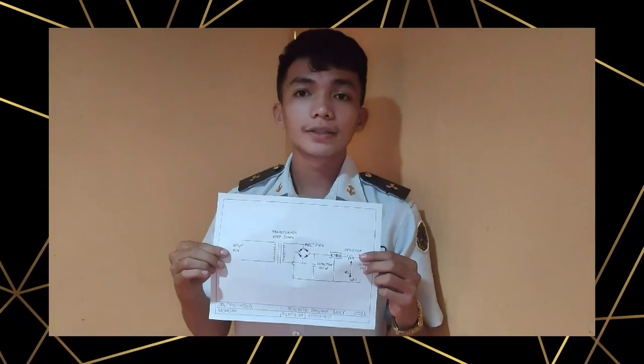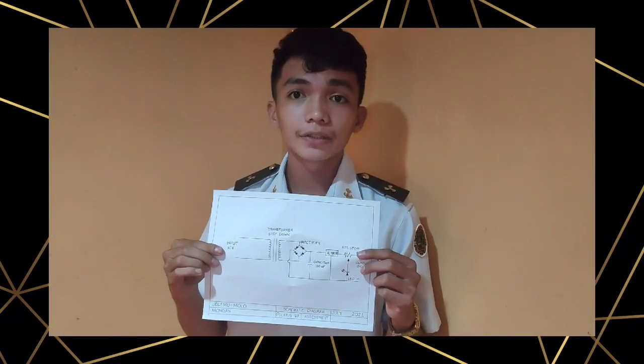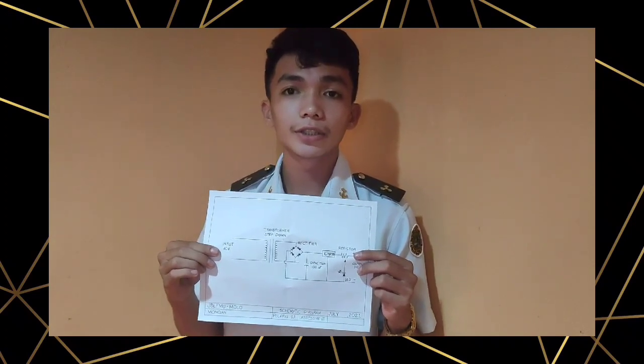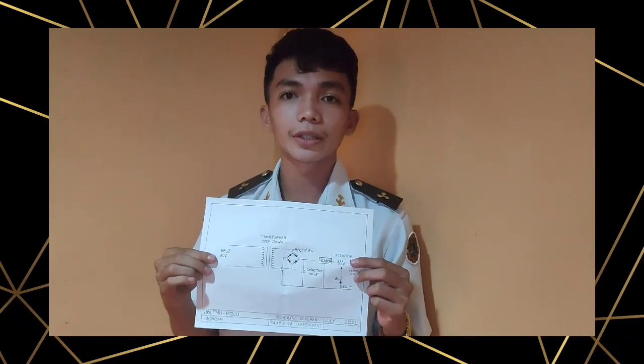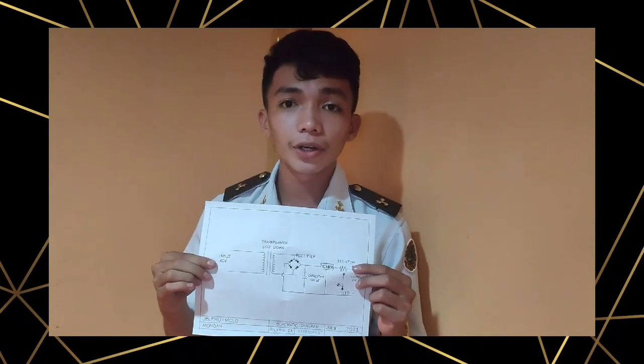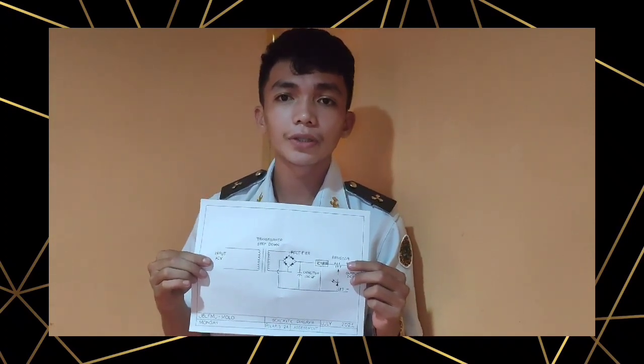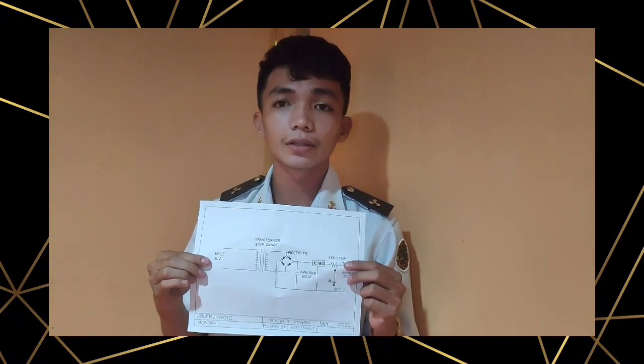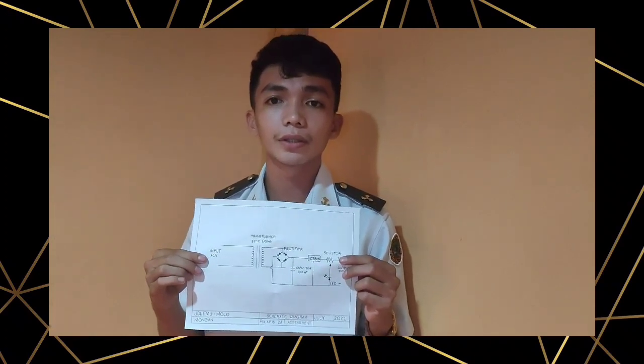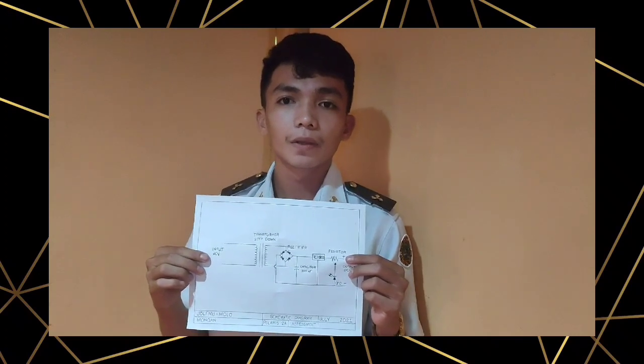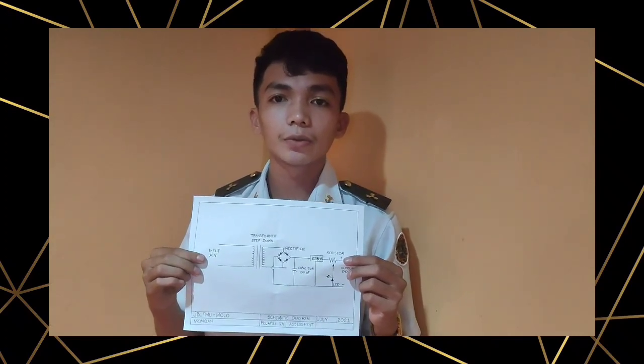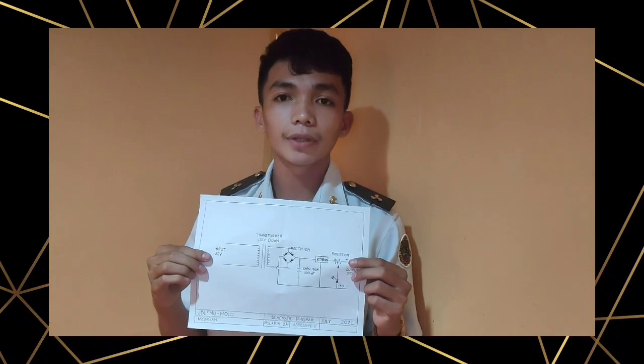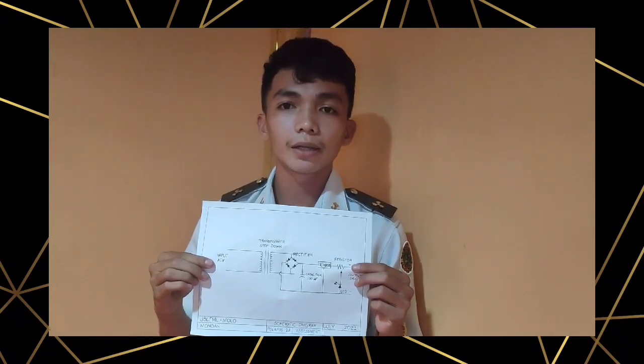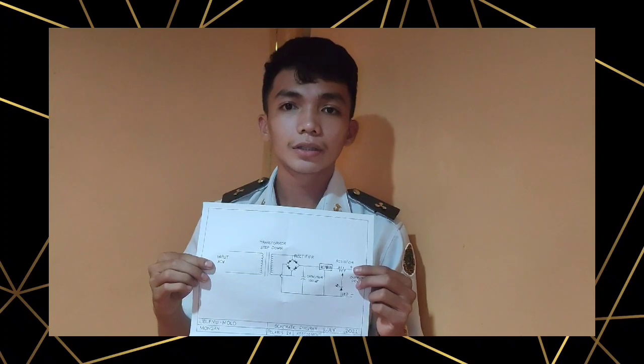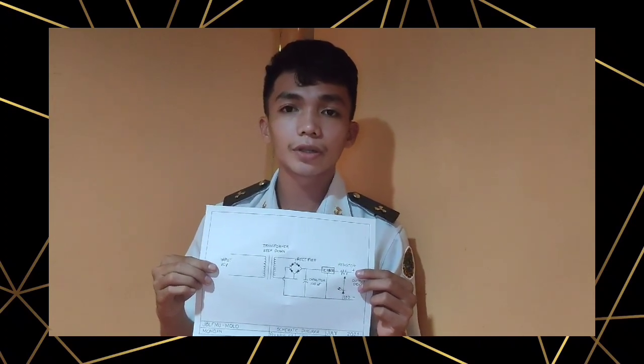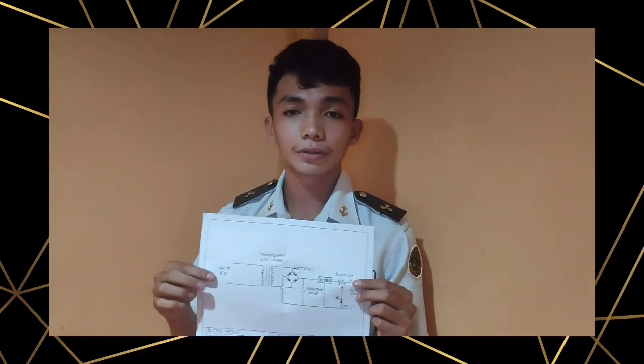The stack is the actual rectifier and is comprised of a set of silicon diodes or selenium plates that function as unidirectional current valves. The diodes or plates are configured so that AC flows in one direction and is blocked in the other, resulting in both halves of the AC wave flowing in the same direction. The cabinet, which includes the test panel, safely houses these components and allows for monitoring and other advanced operations.